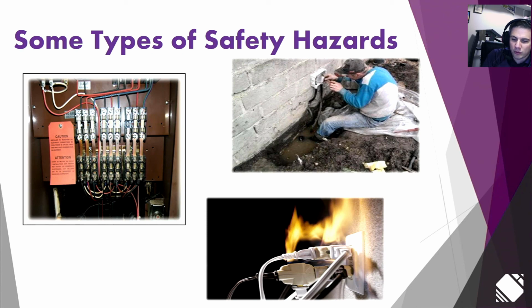Something as an example from my own personal life: when my wife and I sold our first house, part of the purchase for the new owners was to have a CSA certified inspector come in and look at everything. I had changed some of the breakers around, added plugs over the years, everything to code, but when the inspector came in and looked at it, they actually found that the 220 volt plug from the breaker up to our stove, which I had never touched - it was there long before me - whoever installed it didn't tighten the lug tight enough inside the breaker panel, so the copper was making a connection, but it was loose.